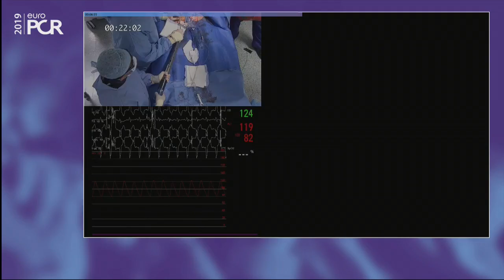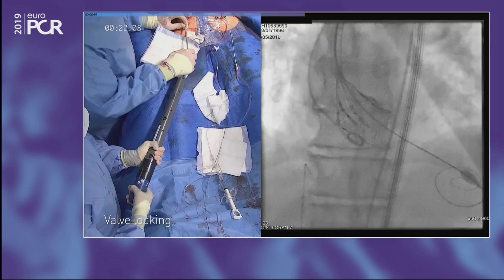Hemodynamics are better. So the nose cone wire, we just need to make sure that the nose cone has plenty of room to run, and it's got to extrude out a little bit more just as we release this valve. It's all beginning to really align now. There's no risk of twisting with this new design of the pillars and the posts. Looking at the locking is much easier now with these more radio-opaque markers. So it's just slowly allowing the valve to lock. There's a nice waist on this valve.